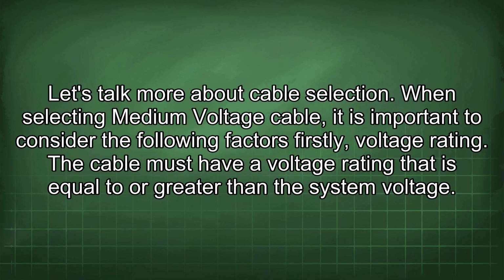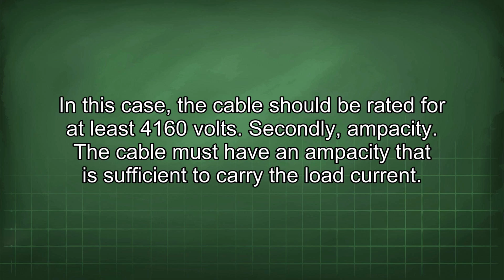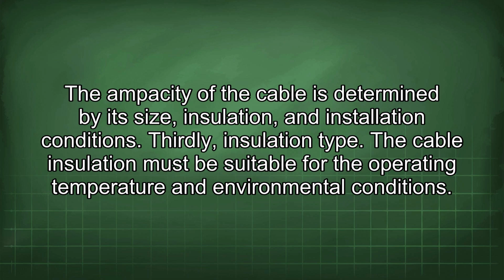When selecting medium voltage cable, it is important to consider the following factors. Firstly, voltage rating. The cable must have a voltage rating that is equal to or greater than the system voltage. In this case, the cable should be rated for at least 4160 volts. Secondly, ampacity. The cable must have an ampacity that is sufficient to carry the load current. The ampacity of the cable is determined by its size, insulation, and installation conditions.